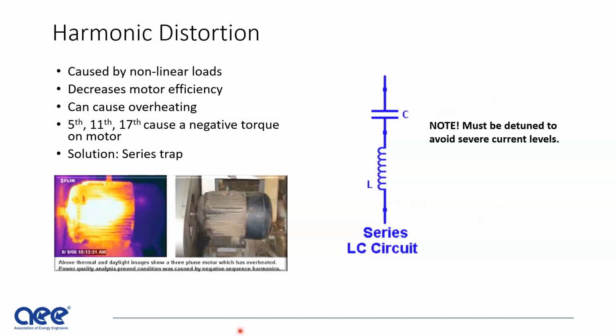Harmonic distortion is treated using a series trap circuit. You can use different types of detuned trap circuits. The reason you want it detuned is that this literally is a short circuit at the frequency of the 5th harmonic. So at 300 hertz, which is the 5th harmonic, this would be a dead short and you'd have a very high current, and you don't want that. So you do detune them a little bit.